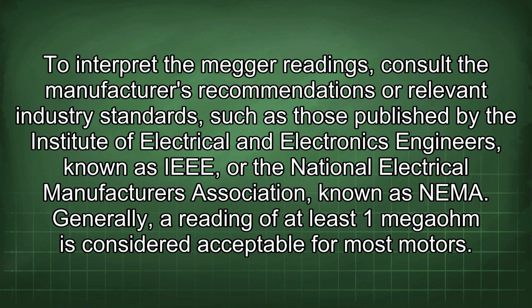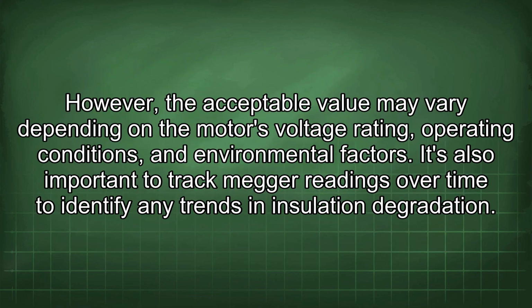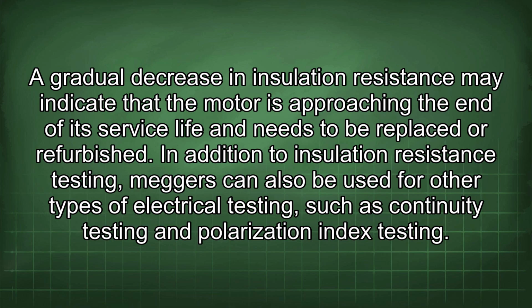To interpret the Megger readings, consult the manufacturer's recommendations or relevant industry standards, such as those published by the Institute of Electrical and Electronics Engineers, known as IEEE, or the National Electrical Manufacturers Association, known as NEMA. Generally, a reading of at least 1 megohm is considered acceptable for most motors. However, the acceptable value may vary depending on the motor's voltage rating, operating conditions, and environmental factors. It's also important to track Megger readings over time to identify any trends in insulation degradation. A gradual decrease in insulation resistance may indicate that the motor is approaching the end of its service life and needs to be replaced or refurbished.